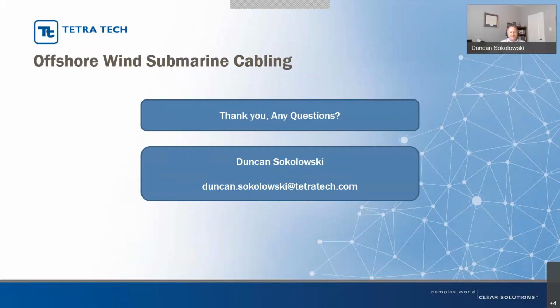Yeah, so the cable burial risk assessment will give a recommended depth of lowering along the route. That can be followed up by a burial assessment study, which tells you how to achieve that burial. It looks at soil types, the recommended DOL, and you come up with a matrix of burial machines that will have a good success of achieving that, or less. It's quite possible to have a mix of burial and installation methodologies along the same cable - that's quite common.